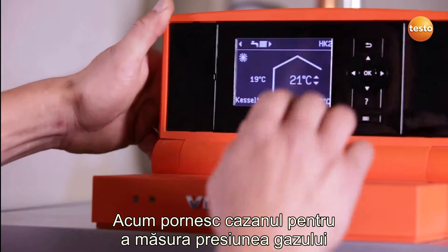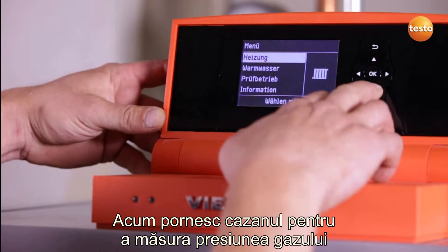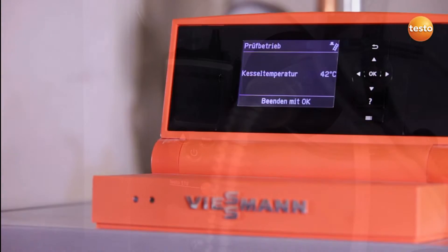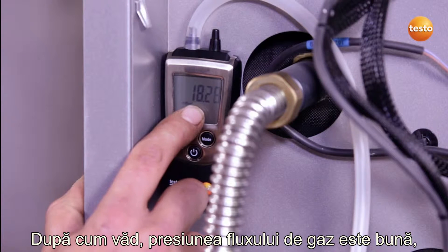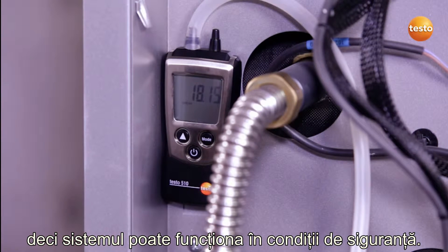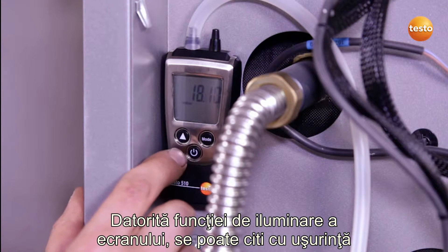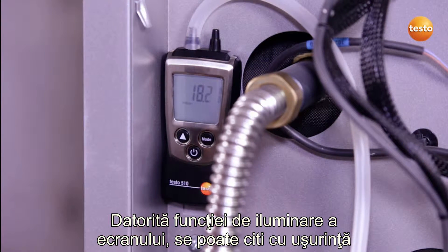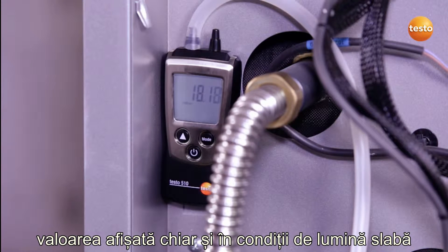I'm now going to start up the system so I can measure the gas flow pressure. As I can see, the gas flow pressure is OK, so the system can be operated safely. Thanks to the Testo 510's backlit display, I can read off the value clearly and legibly even in poor light conditions.